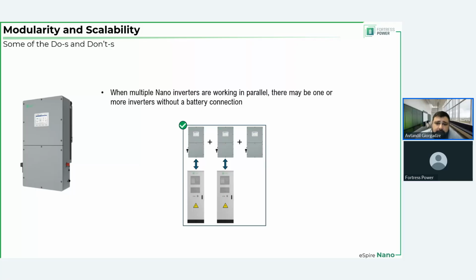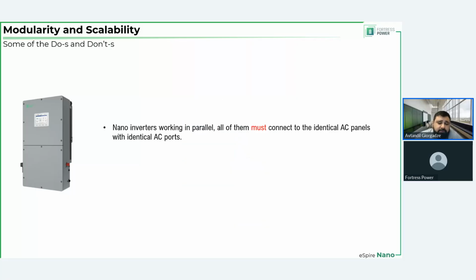And regardless of whether all of the inverters or some of the inverters have batteries connected to them in the parallel inverter group, all of them must connect to the same AC panels with the same AC ports, right? So if you have a backed up load panel, all of the inverters connect to that backed up load panel. If this is a grid-tied system, all of them connect to the panel board from which they take the grid AC power.